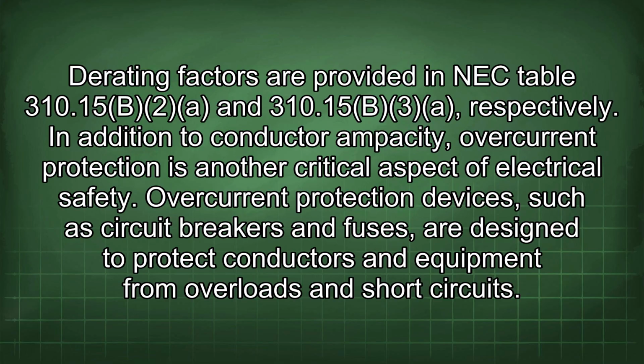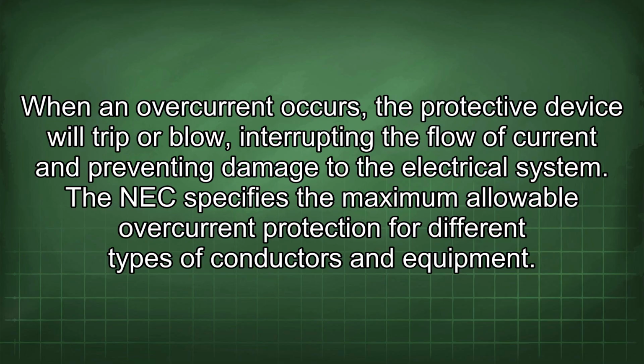310.15(B)(3) respectively. In addition to conductor ampacity, overcurrent protection is another critical aspect of electrical safety. Overcurrent protection devices, such as circuit breakers and fuses, are designed to protect conductors and equipment from overloads and short circuits. When an overcurrent occurs, the protective device will trip or blow, interrupting the flow of current and preventing damage to the electrical system. The NEC specifies the maximum allowable overcurrent protection for different types of conductors and equipment.